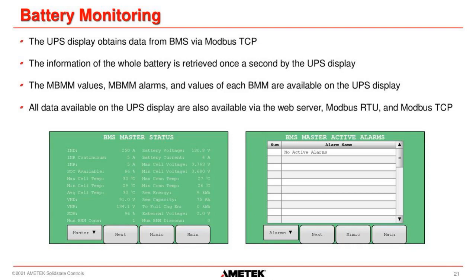You can see the alarms of the whole battery, all the cabinets. They're all combined into one alarm, or one interface, by the battery itself. So you can see alarms for each cabinet or for the whole battery. And all the data that's available on the UPS display is also available on the web server, Modbus RTU, and Modbus TCP.